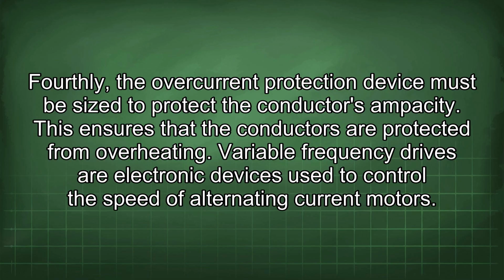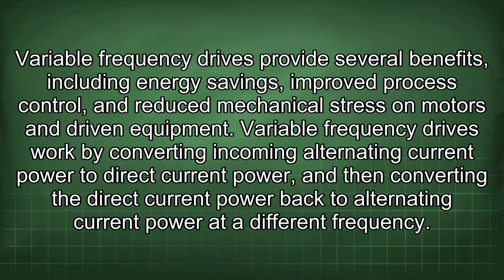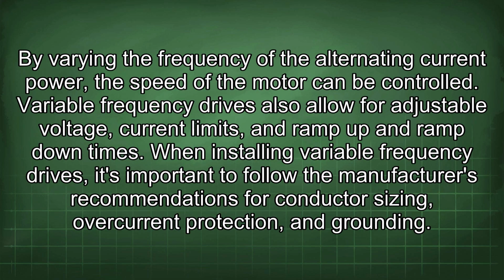Variable frequency drives are electronic devices used to control the speed of alternating current motors. Variable frequency drives provide several benefits, including energy savings, improved process control, and reduced mechanical stress on motors and driven equipment. Variable frequency drives work by converting incoming alternating current power to direct current power, and then converting the direct current power back to alternating current power at a different frequency. By varying the frequency of the alternating current power, the speed of the motor can be controlled. Variable frequency drives also allow for adjustable voltage, current limits, and ramp up and ramp down times.